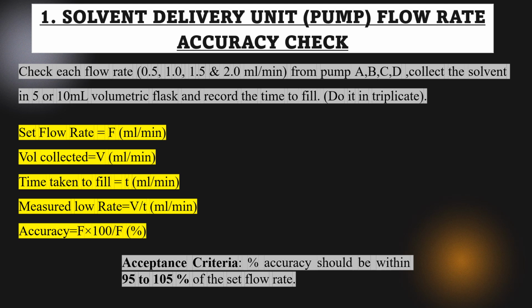You need to calculate the accuracy of this flow rate. That is going to be the flow rate into 100 divided by the measured flow rate, so that is going to give you the percentage. Now the acceptance criterion for this is 95 to 105% of the set flow rate.